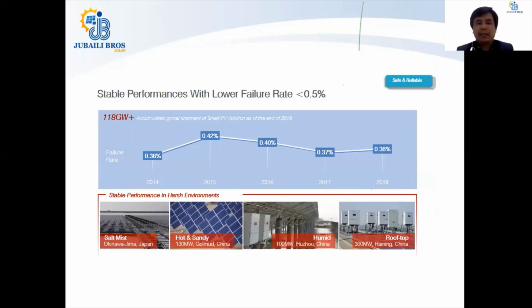Again, with reliability, we have a very low failure rate of our inverters. In 2014, the failure rate was 0.36 and slightly increased to 0.42 until now. The latest figure that we have, in 2018, the failure rate was 0.38 in terms of global supply of our inverters. Huawei has supplied 118 gigawatts plus till the end of 2019, and we are very sure that our inverter failure rate is less than 0.5%, which you can consider while you are simulating a PV system as well.